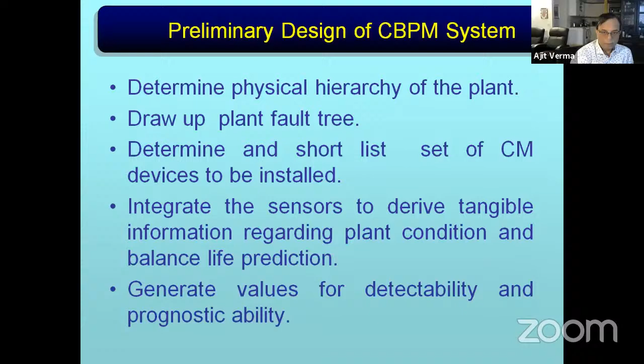For example, under this system you have a module, such as the diesel generator module or the air conditioning plant, under condition-based predictive maintenance. Is the condition within the threshold? If not, increase the rate of condition monitoring and check the condition again. If still not within threshold, add some prognostic features, then check the condition-based monitoring status, and decide on the required level of maintenance.